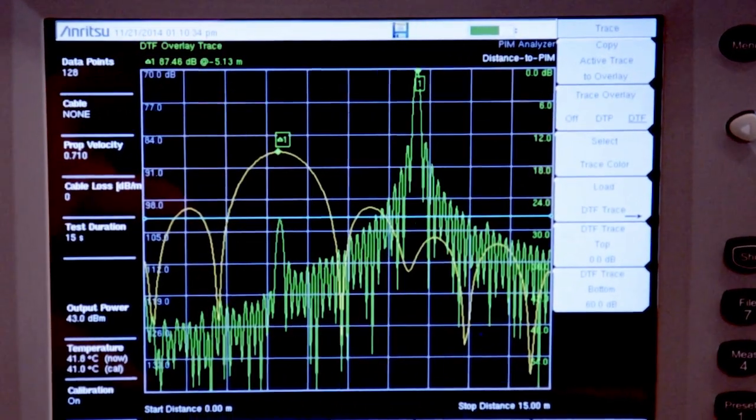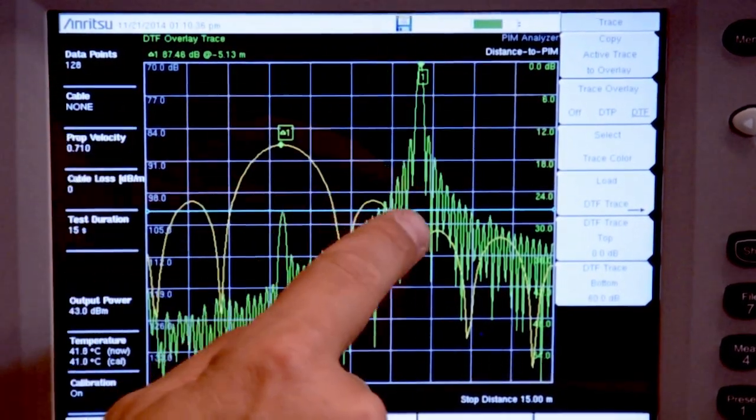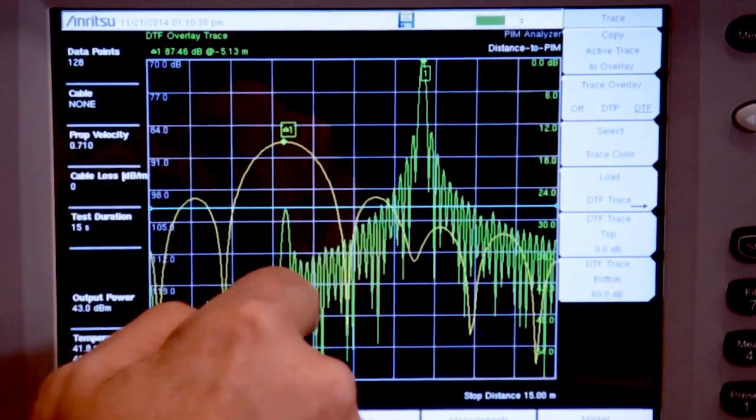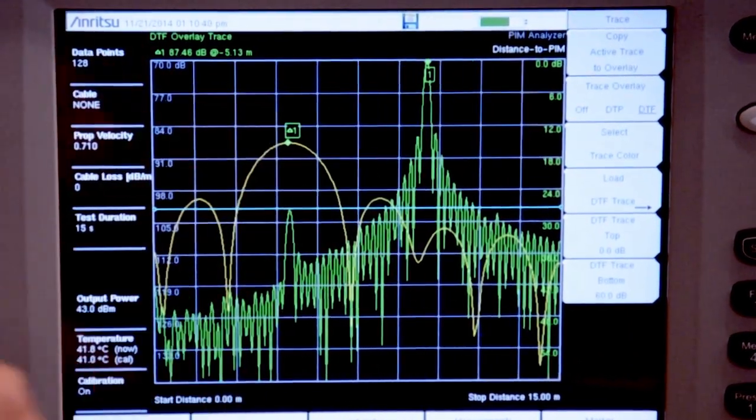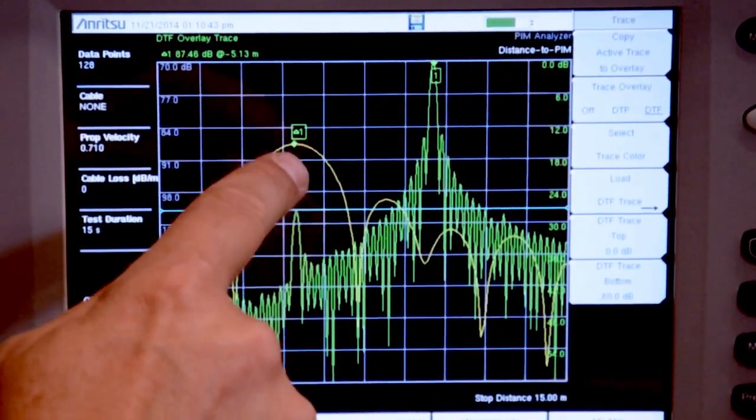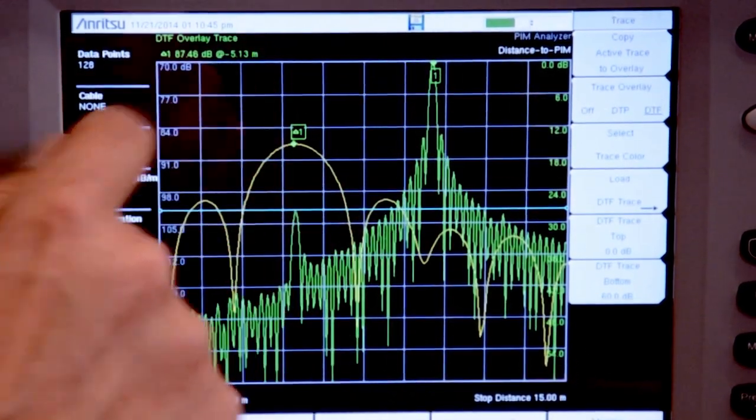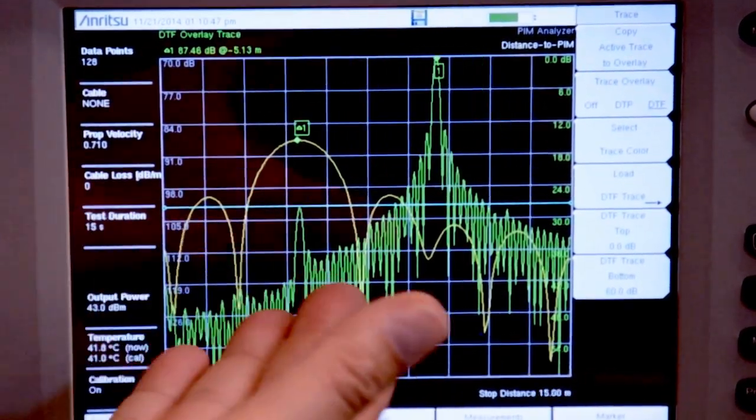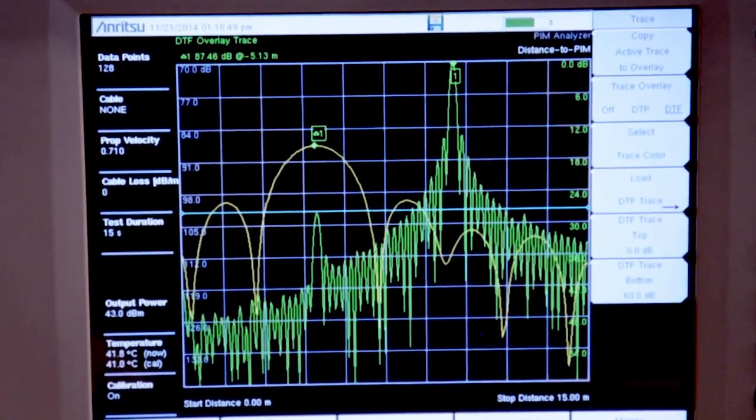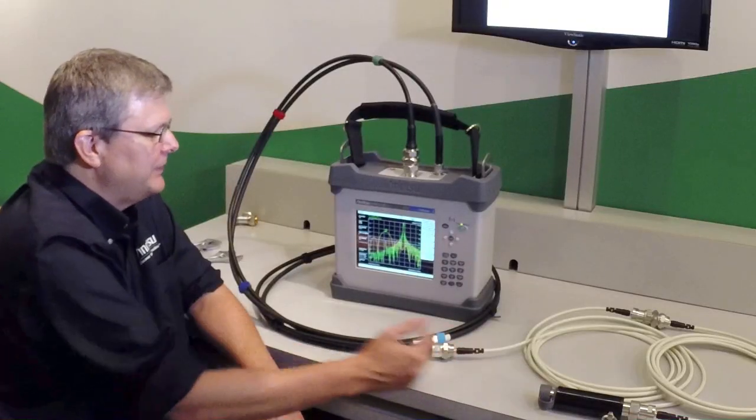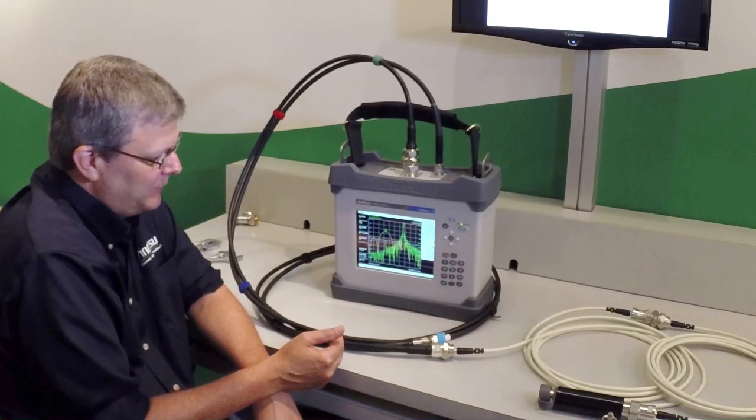What this tells me is that if I look at the location of where we know the end of the cable was and look at the location of our PIM fault, a delta marker has been set up and it tells us that it's minus 5.13 meters. So more information about the location of this PIM - we know that it's five meters closer to the instrument than the end of the cable.